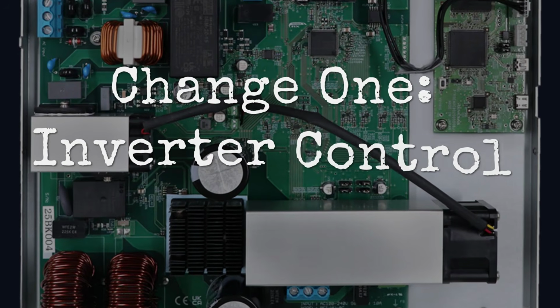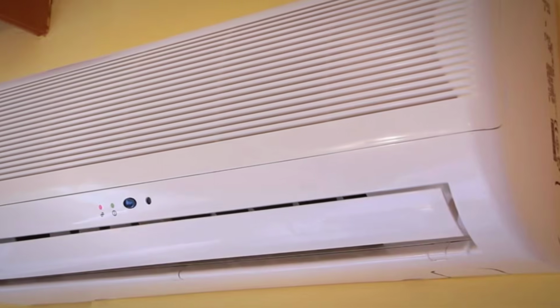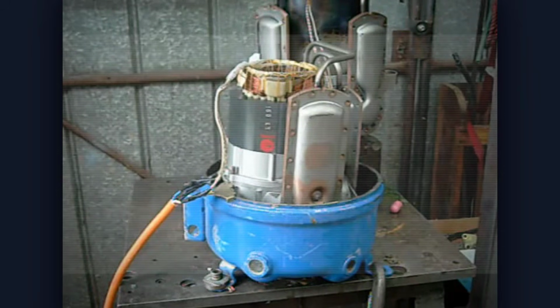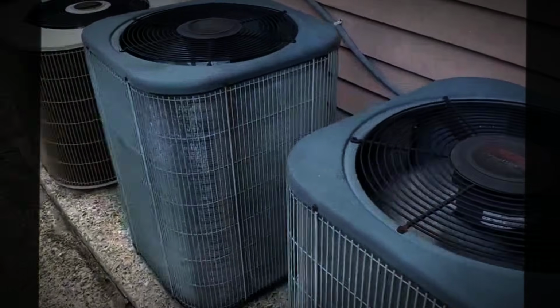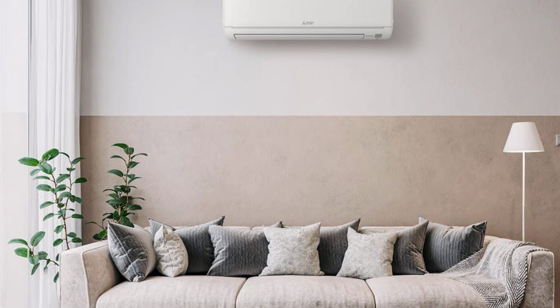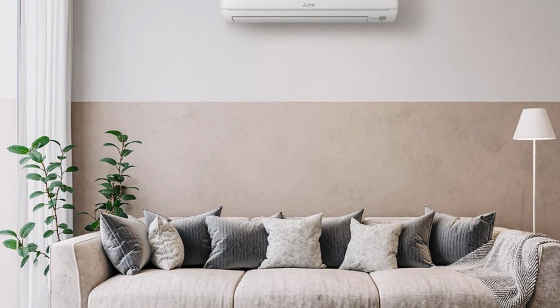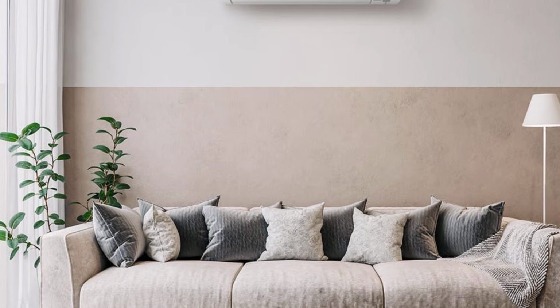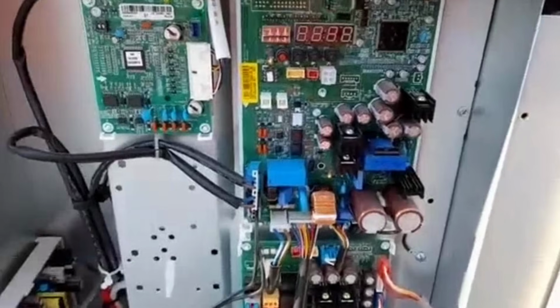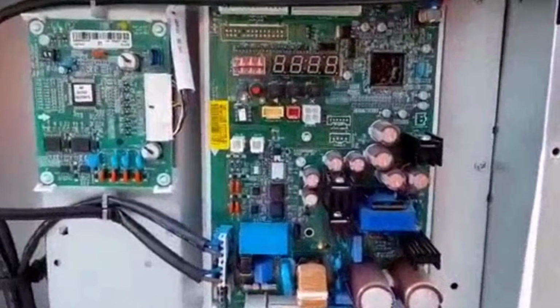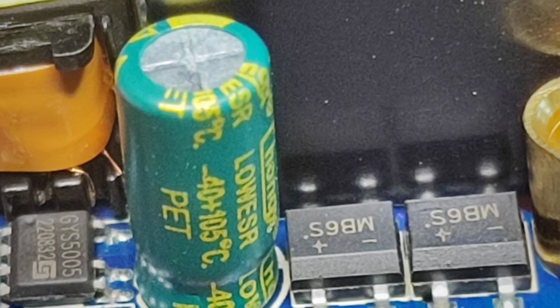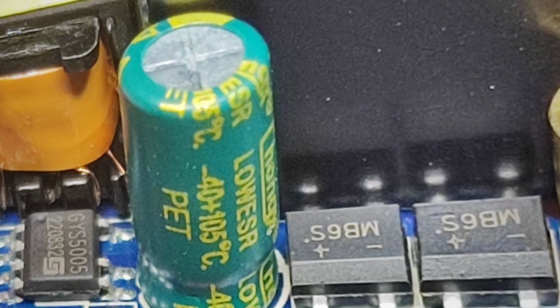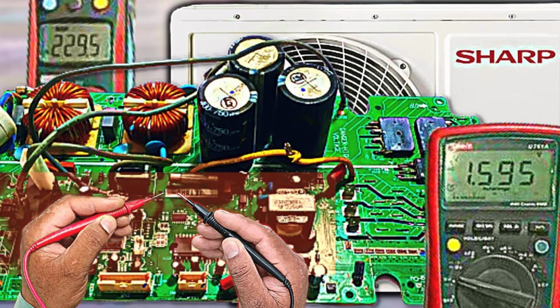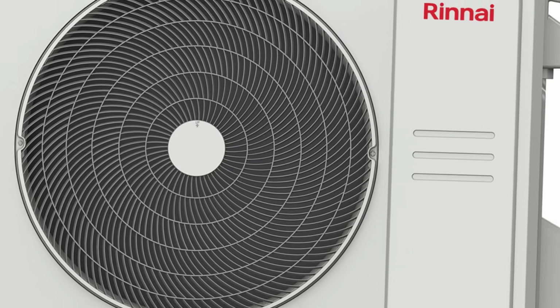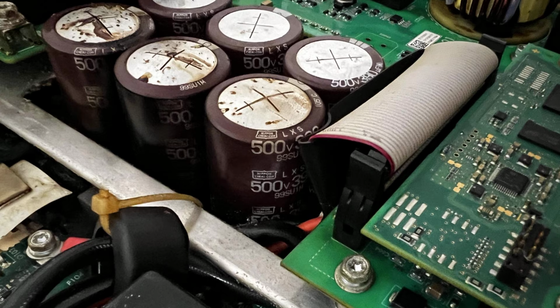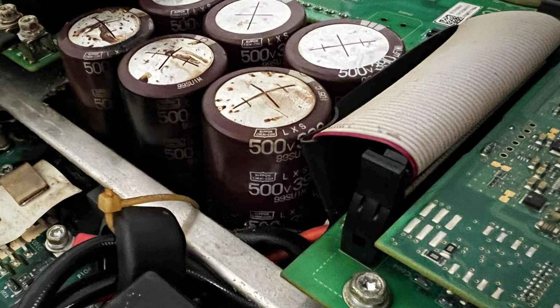Change 1, the inverter control board. Modern split systems use inverter technology. An inverter varies compressor speed based on demand, rather than switching the compressor fully on and off. On paper, it is genuinely better technology, more efficient, quieter, and better at temperature control. The problem is not the concept. The problem is the components used to build the board. A quality inverter board uses capacitors rated to 105 degrees Celsius, with a voltage tolerance buffer well above normal operating conditions. A builder-grade residential unit uses capacitors rated to 85 degrees Celsius with almost no buffer.